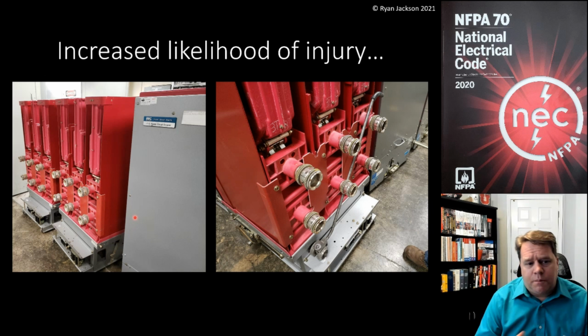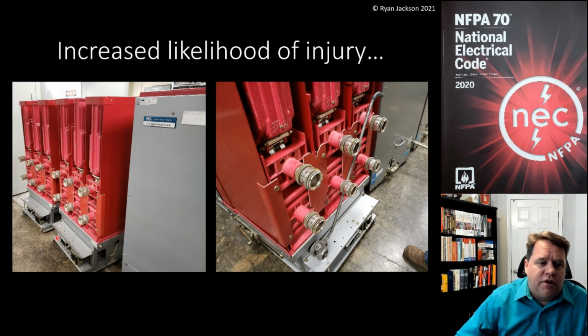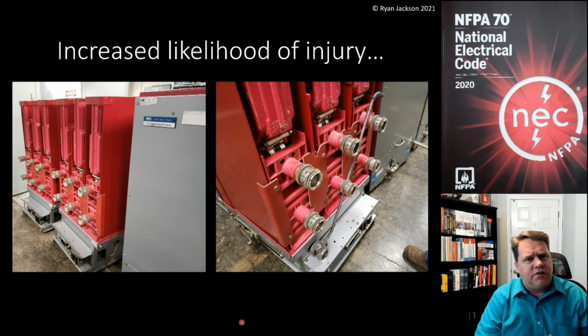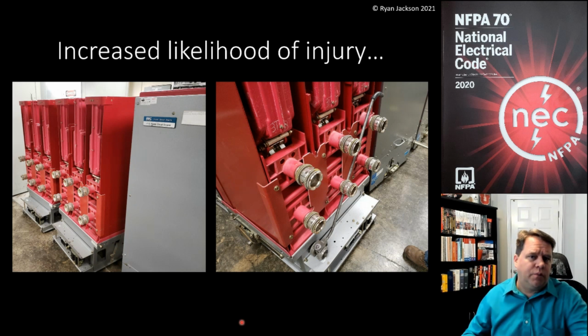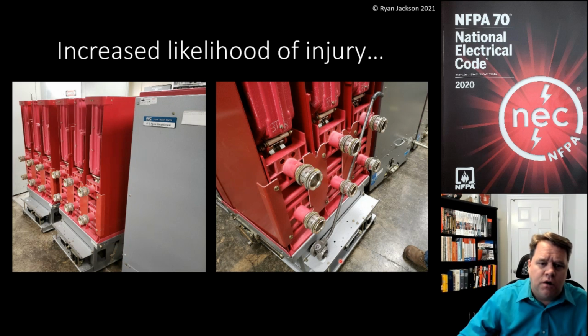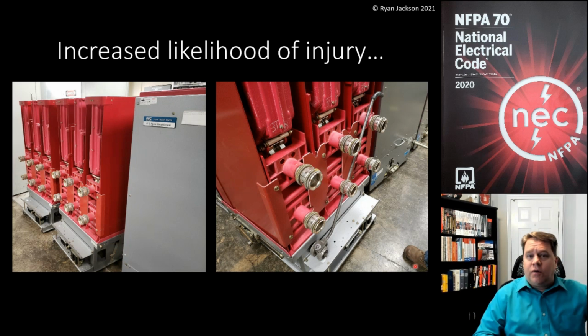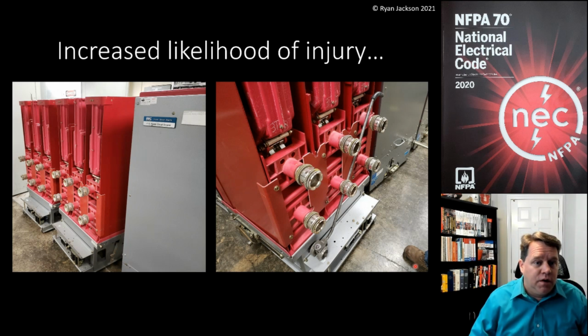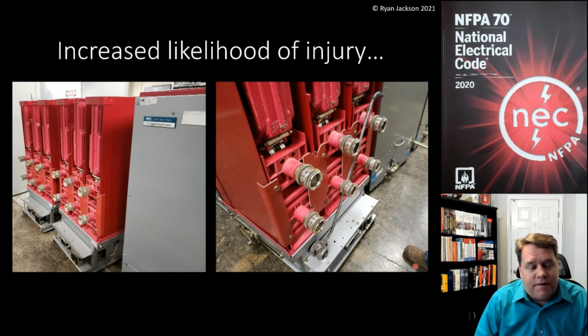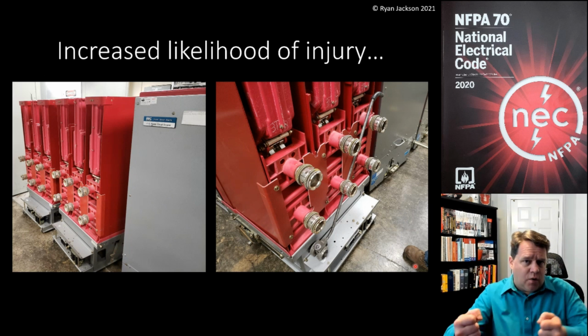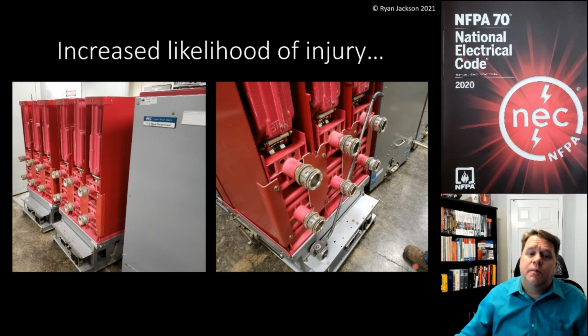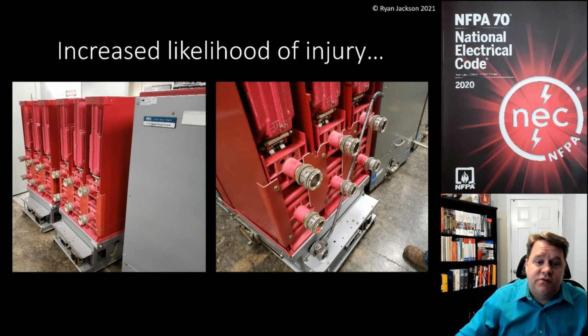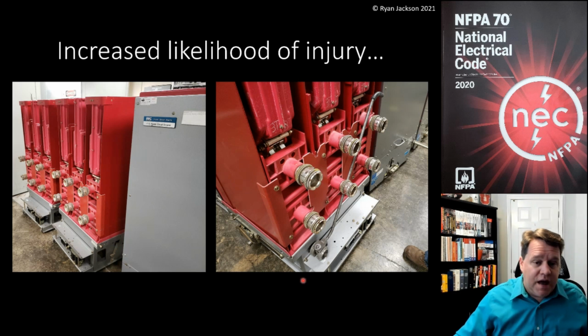Now, one of the components to these large circuit breakers is they're on kind of a dolly system, if you will. And to move them from point A to point B, you put this bar inside of there and you drag it around, kind of like the handle of a wagon, if you will. So, what we're looking at in this photograph here is an actual incident, a near miss, as it's called. This is at a place where I teach every year. They had racked out this circuit breaker, and when they pulled it out, they realized that someone, potentially years ago, had left this bar inside of the equipment.